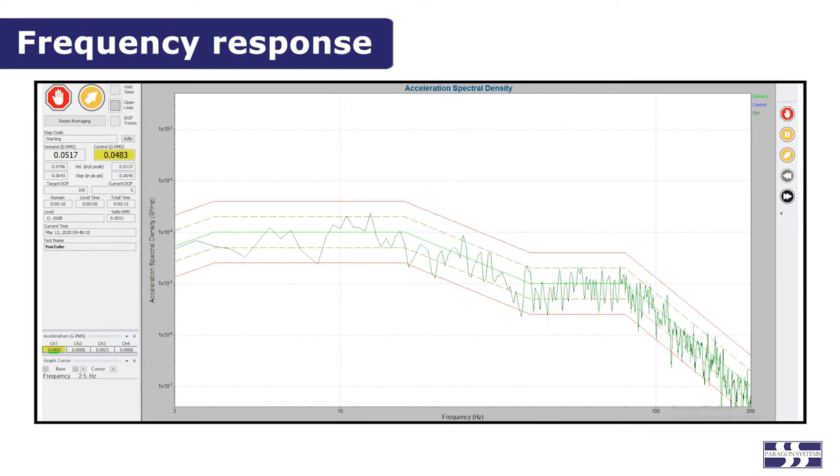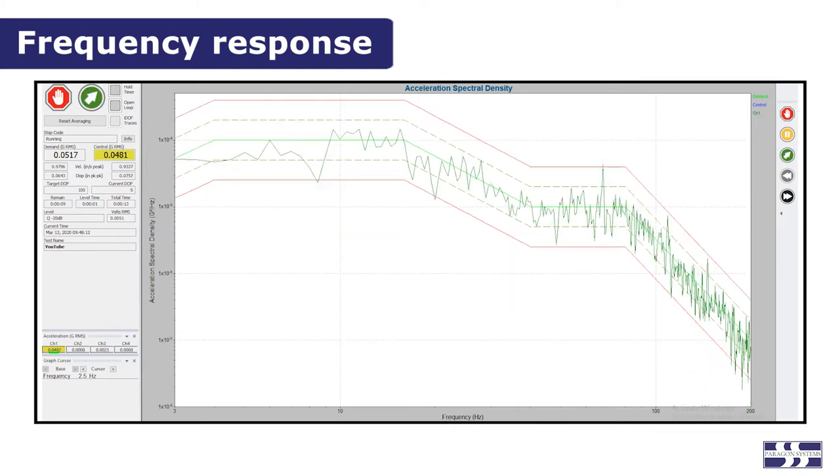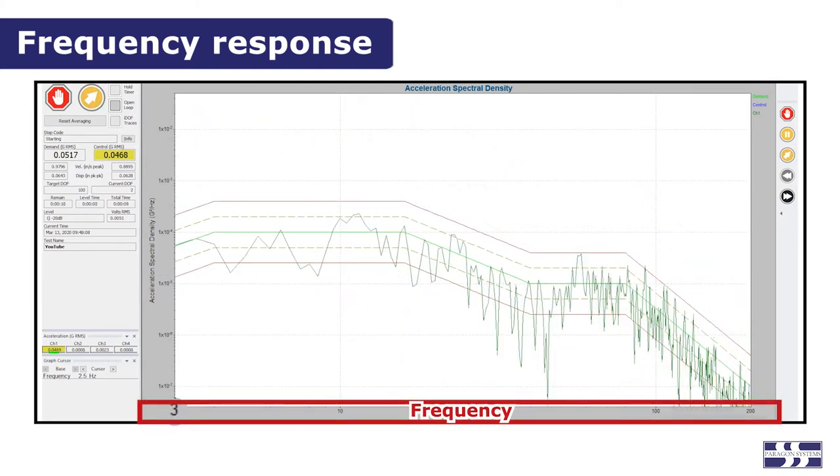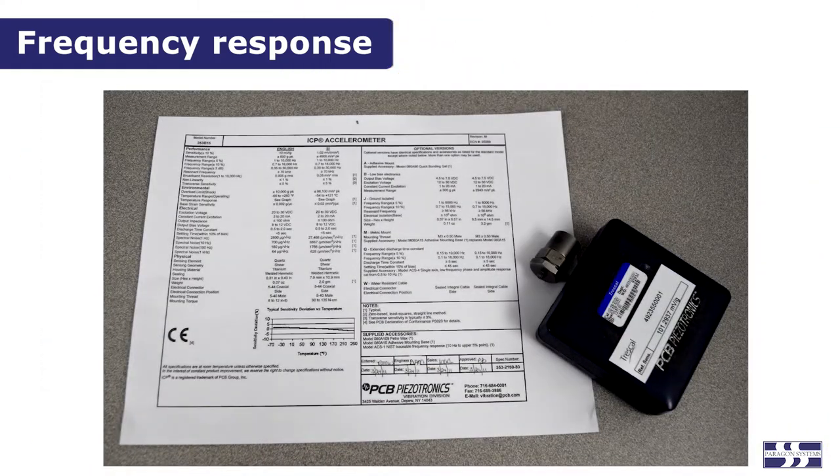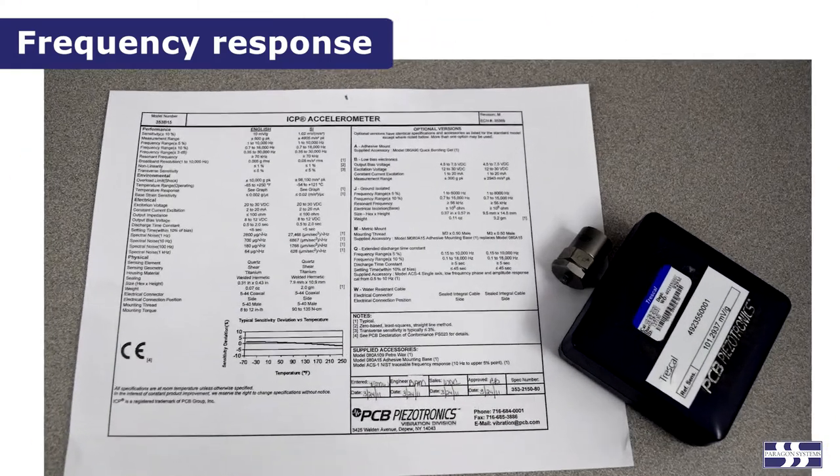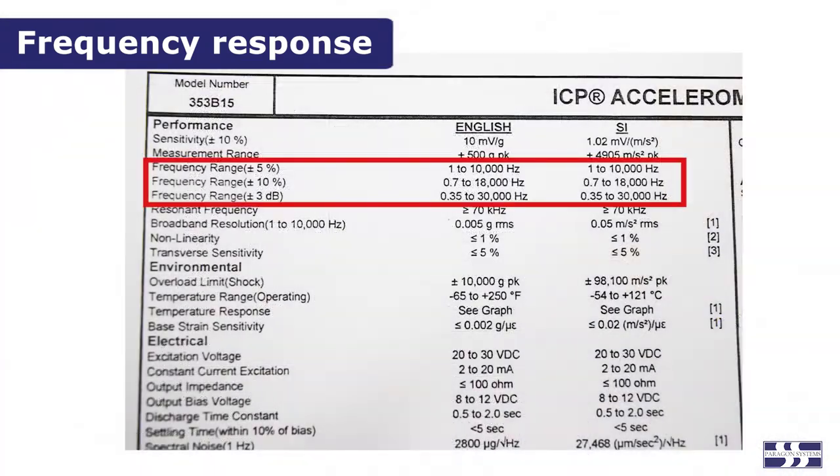Because of this, it's necessary to match the frequency response of the accelerometer to the frequency range of your test profile. The manufacturer's specification for the accelerometer will define the acceptable frequency range for the accelerometer.